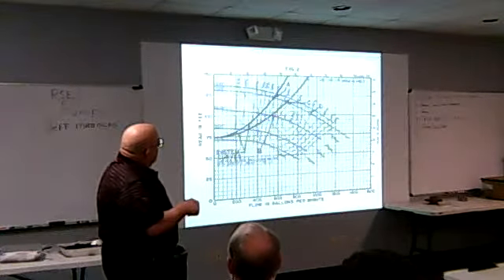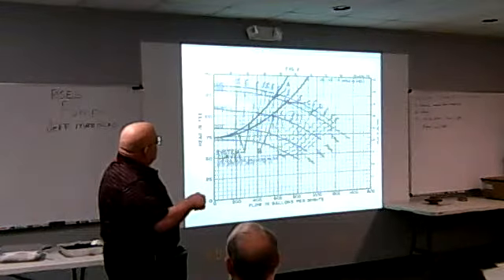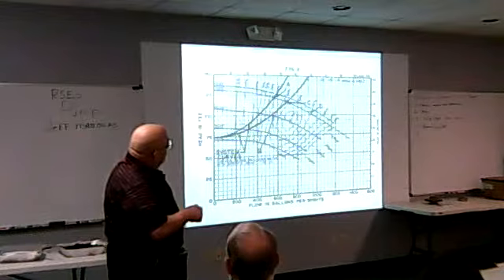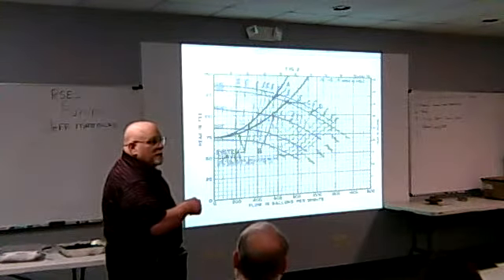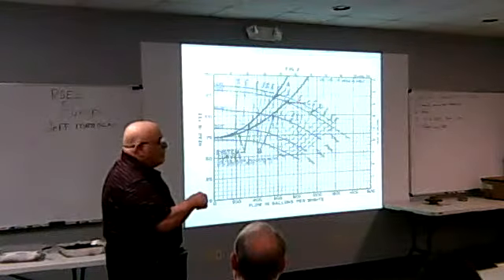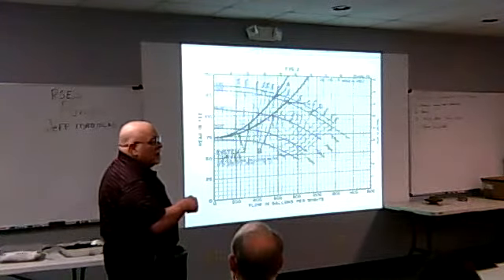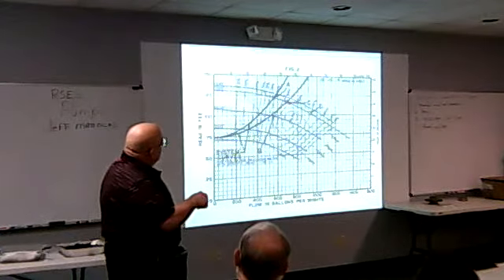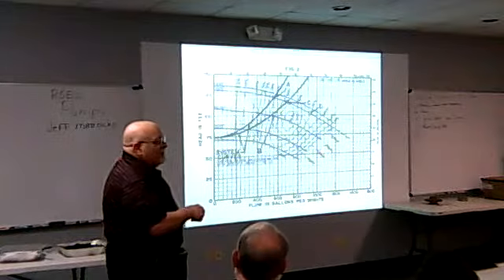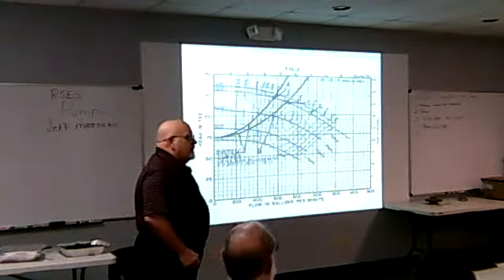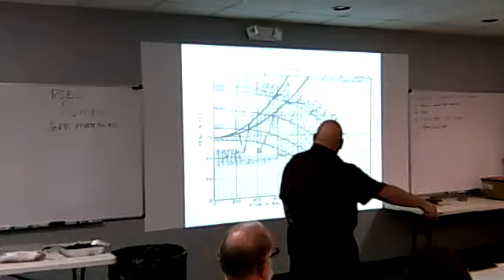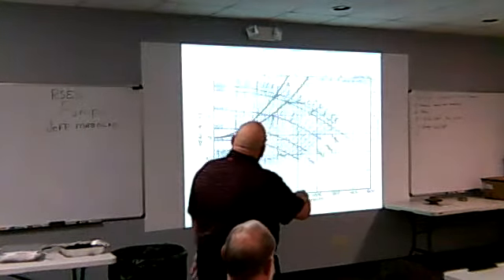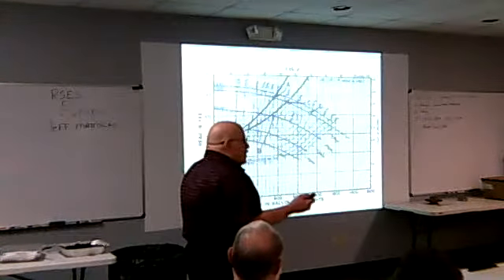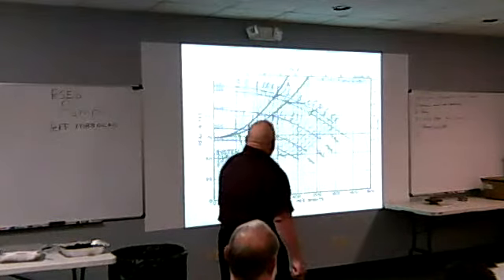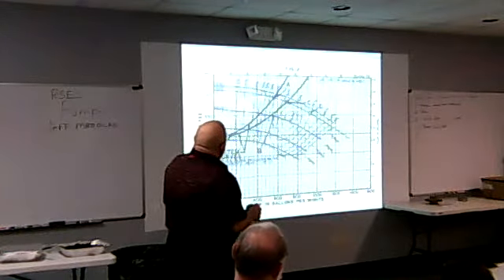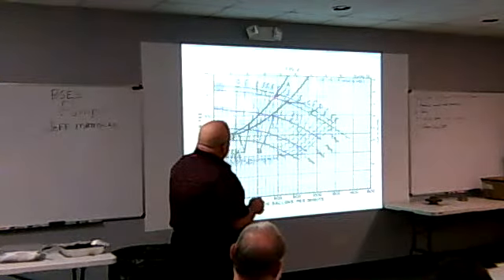So if I do a design, and we actually wind up here, I can come in, if I have my system curve, and say, let's trim this impeller to 10.1. Now my system curve is right where my new impeller cut is. I'm not producing all this extra horsepower. I'm down in this horsepower range. I'm below 20 horse now. If I'm full impeller, I'm at 25 horse. If I trim the impeller, I'm less than 20. I'm saving energy. And this is what VFD trimming is this way? Yeah, you just cut an inch off. This one says 10.8. This one was right here. I can trim it down to 10. Smaller OD. Yeah. Less horsepower. I'm saving energy by doing it. Okay? But a lot of people, you know, they don't realize like this was original design.